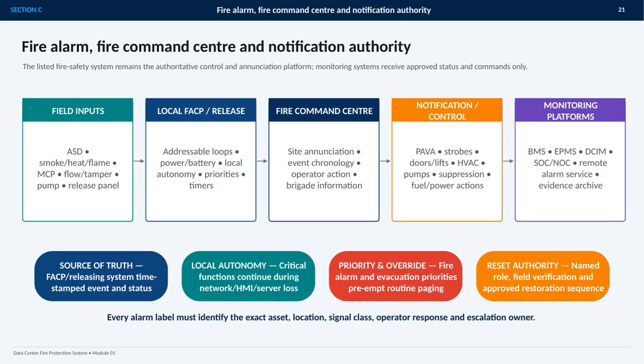This section defines how the fire alarm, fire command center, and notification authority work together. The key principle is the listed fire safety system remains the source of truth. Field inputs, including smoke, heat, or flame detection, manual call points, water flow and tamper switches, pumps, and releasing panels, are received by the local fire alarm or releasing control system. That local system maintains addressable loops, power and battery supervision, priorities, timers, and critical autonomy. The Fire Command Center then provides site-wide annunciation, event chronology, operator guidance, and the information needed by the responding brigade.